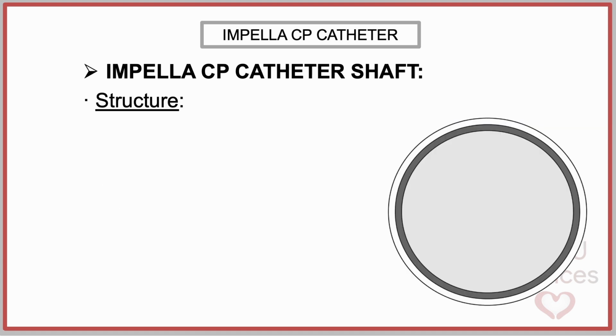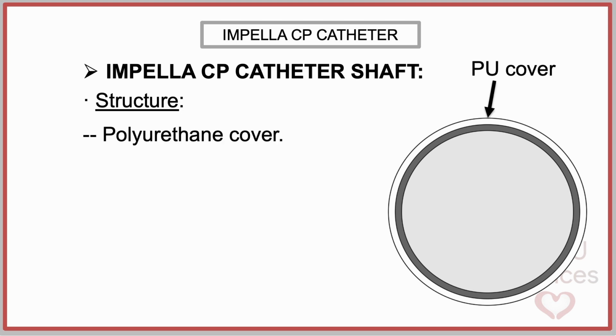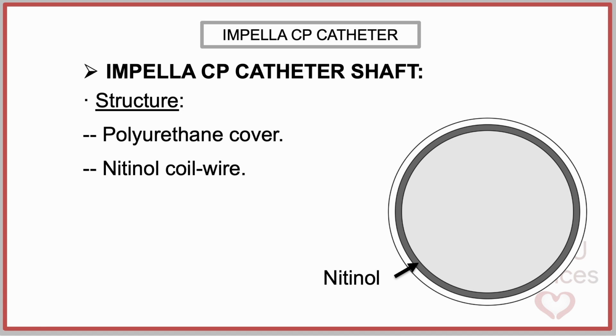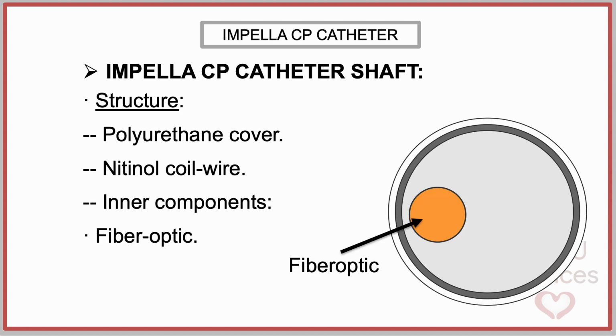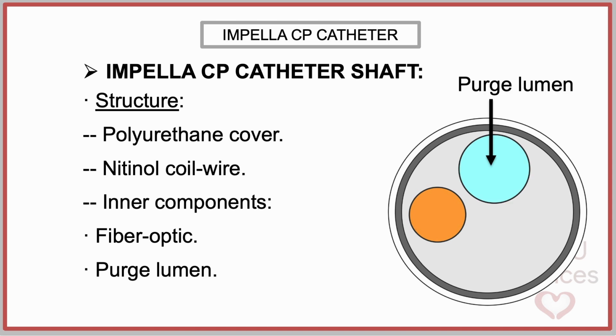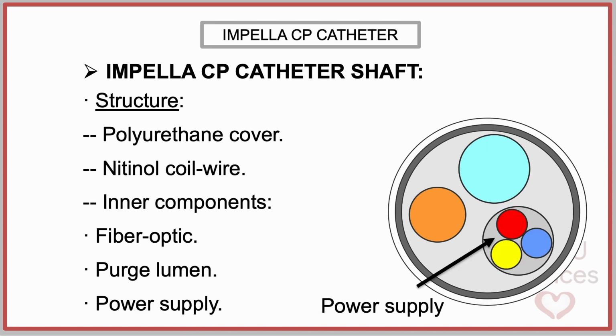The Impella catheter shaft structure consists of a white polyurethane cover with printed marks and numbers. It is reinforced with a nitinol coil wire underneath the cover to prevent the kinking of the shaft, and the three inner components of the catheter shaft that run through the lumen: the fiber-optic cable, the purge lumen, and the motor's power supply, which includes 3 wires corresponding to the three-phase system the motor operates on.